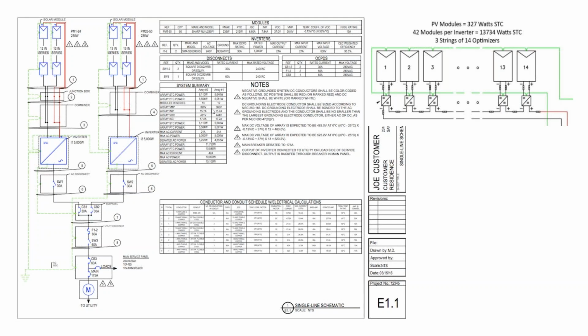There's software you can use, string sizing software that's manufacturer specific, where if you give them the inverter you're using and you give them the solar panels you're using, they will tell you how many modules can be on a circuit. It used to be that you had to have the same number of modules on each circuit and they both had to face the same direction. That's no longer the case.